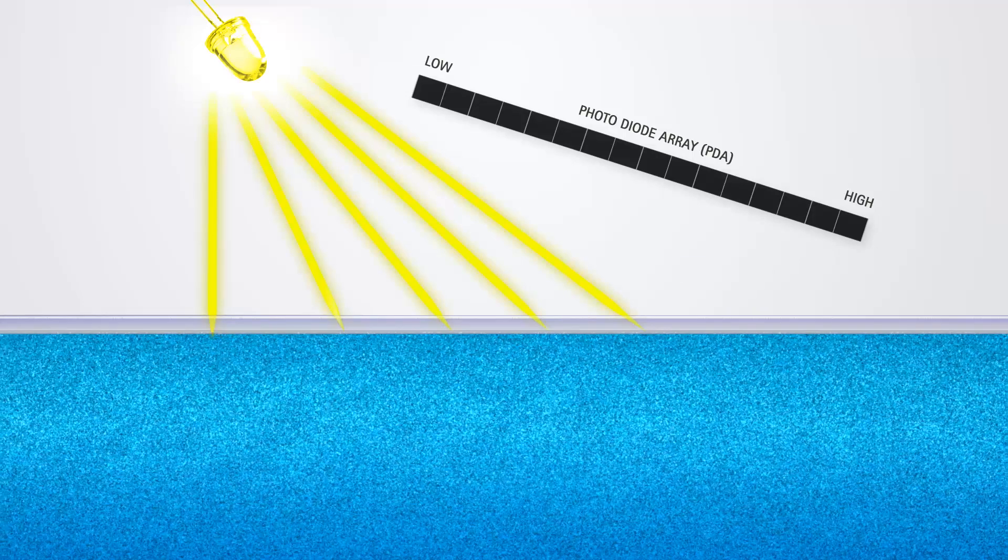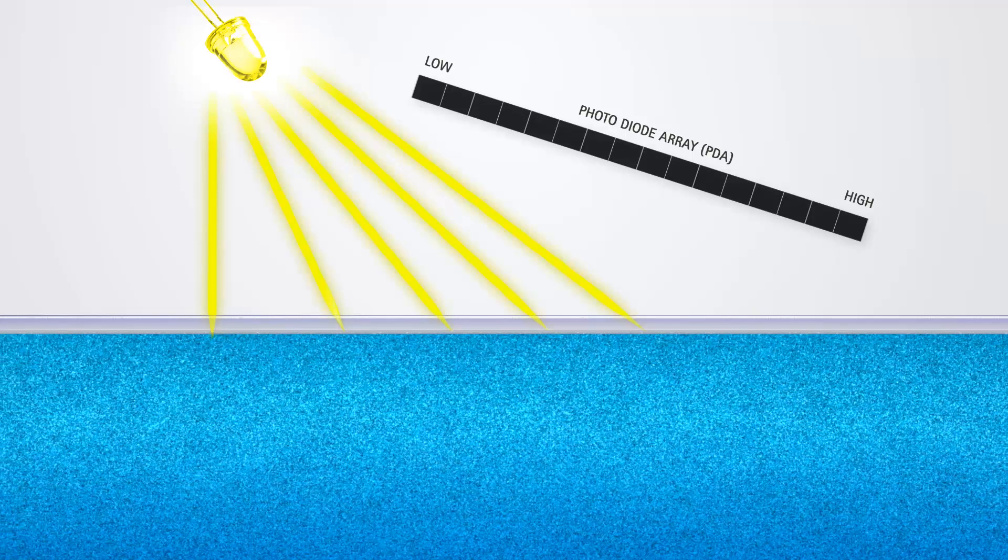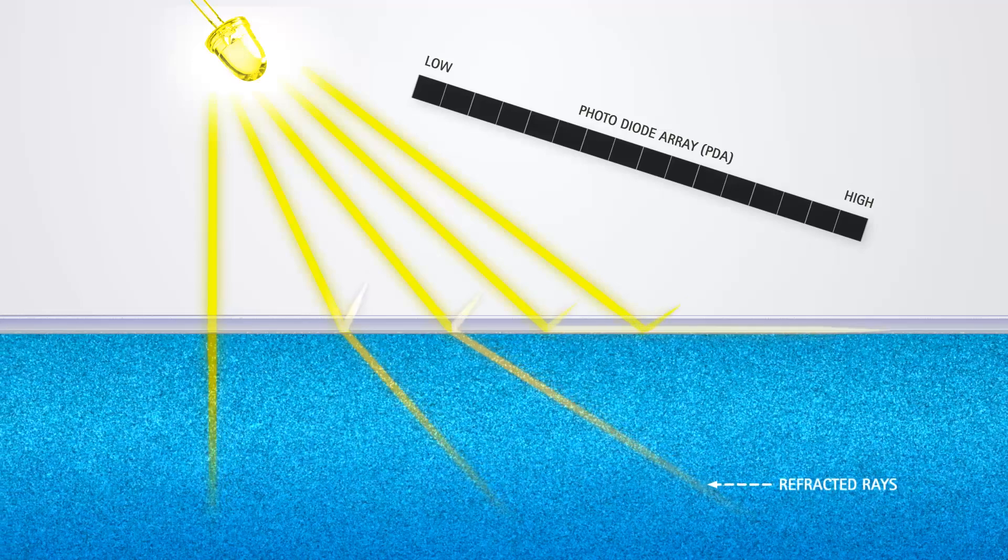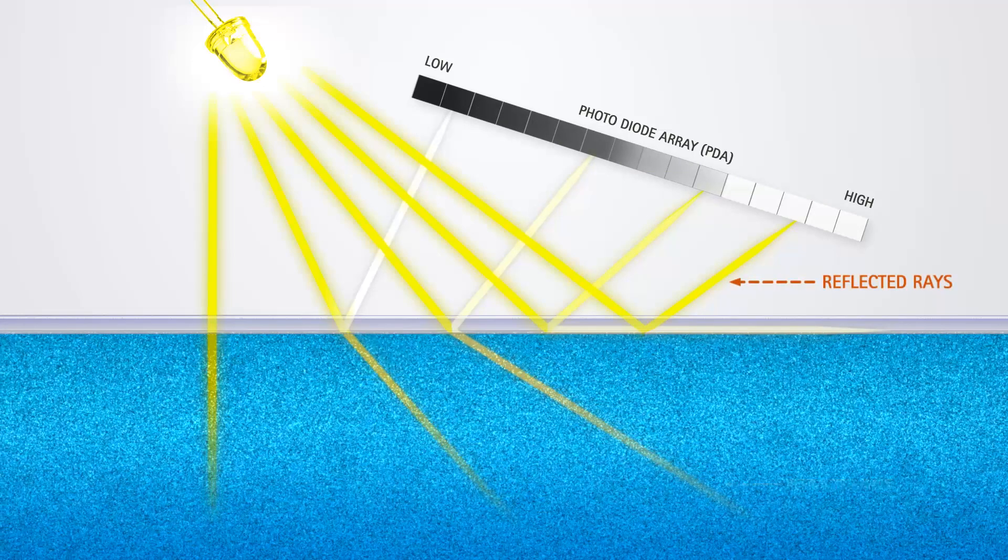When the light from the LED hits the interface between the optical window and the fluid, some of the light is refracted into the fluid and some of the light is reflected back to the photodiode array, or PDA detector.